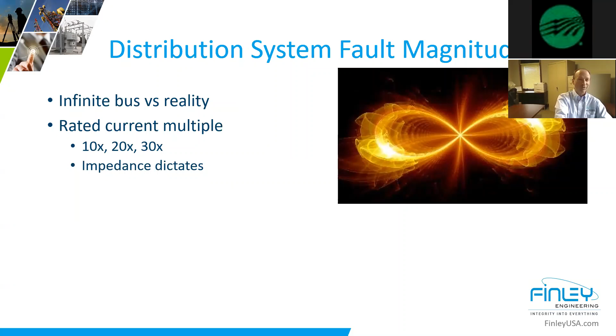So we're not going to have full infinite fault current. We have a multiple of rated current, somewhere in the 5, 10, maybe 20 times, 30 times, depending on how efficient your transformer and facilities are, and how long those copper lines are going out to the service.